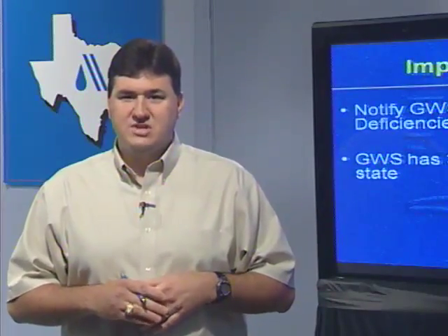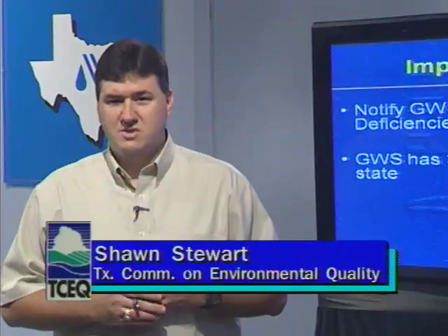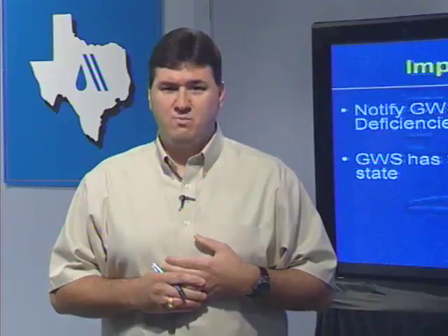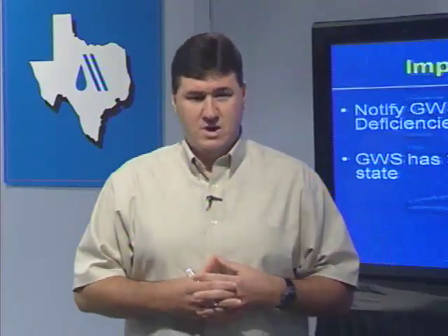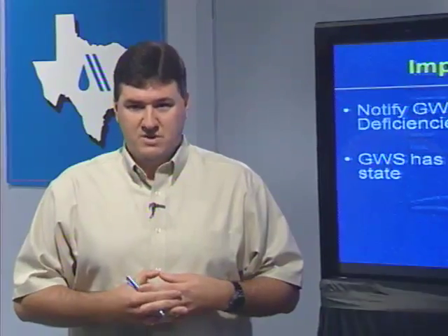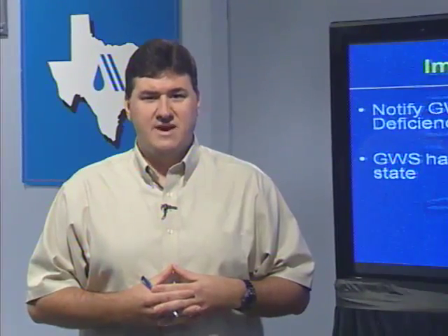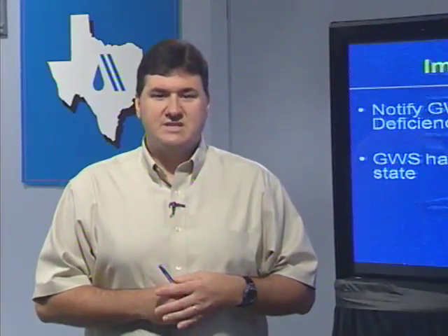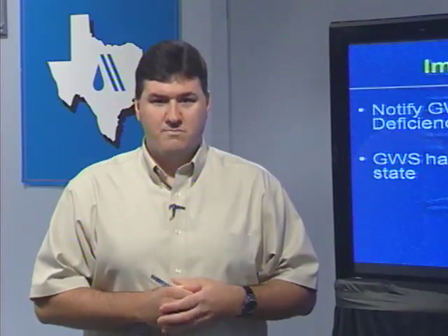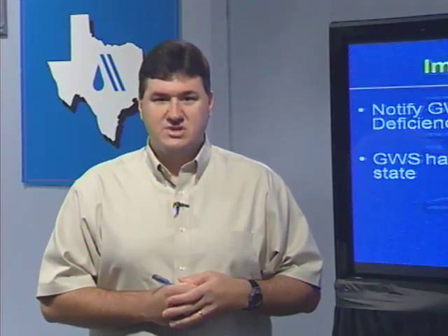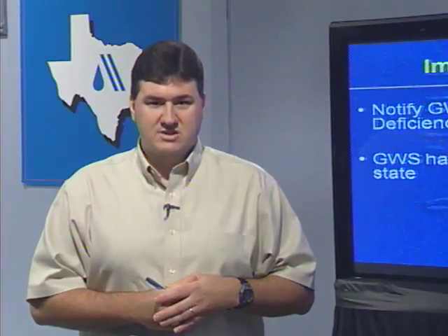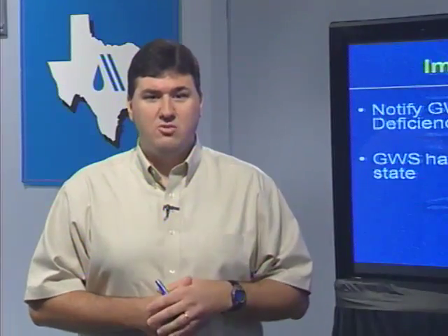Our significant deficiencies are identified in 30 TAC subchapter D. Another component of the groundwater rule is that we have to notify groundwater systems of any significant deficiency within 30 days. We're going to do that through the exit interview process. Those of you who have been through a sanitary survey or CCI know that when an investigator finalizes the investigation, they generally give you an exit interview form outlining the deficiencies.